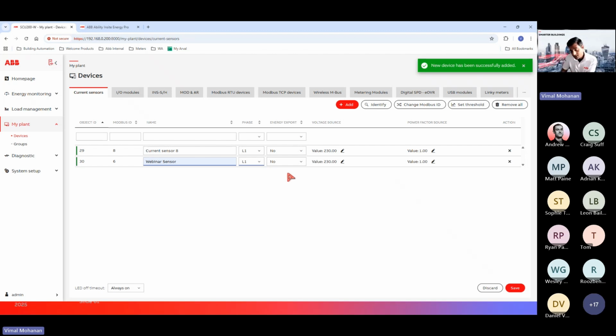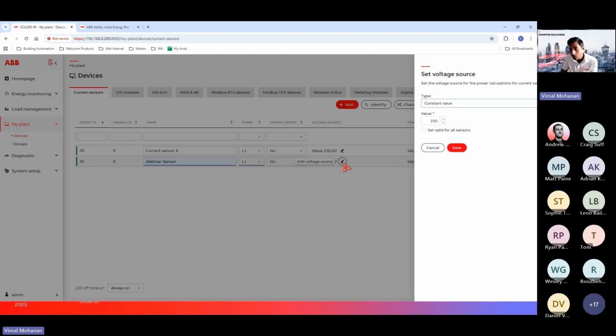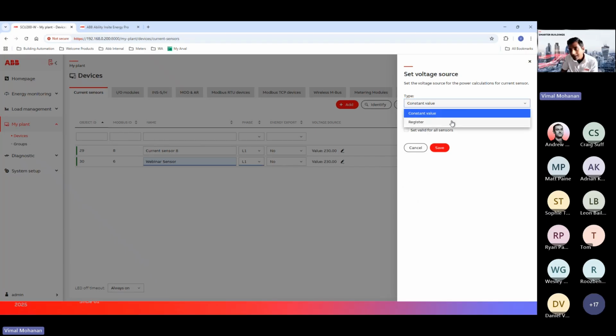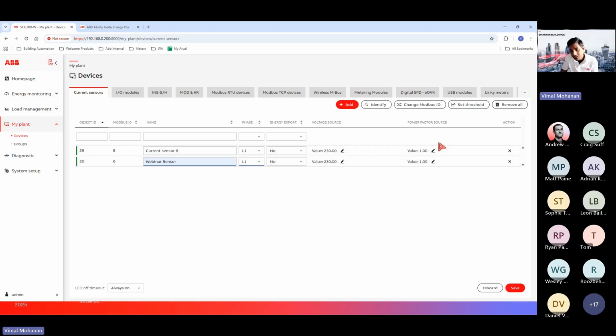Remember, these are current sensors. They're not calculating the voltage. So to calculate the voltage, either you can put a constant value on it, or if there are any meters - in my case I do have a meter, the EQ meter, like we showed on the very first slide, the DIN rail meters, or an M4M meter - I can go in here and pick the voltage, or just give it a constant. Similarly for the power factor. You save it.